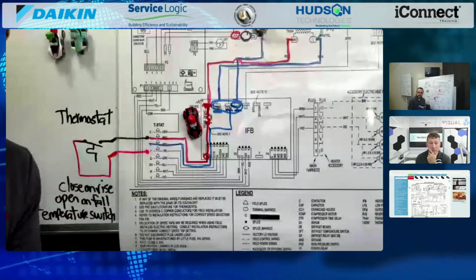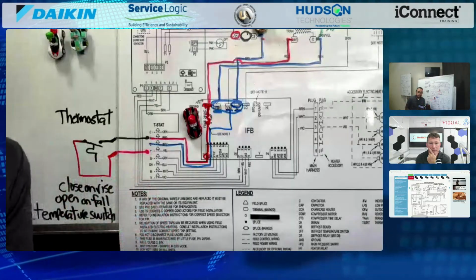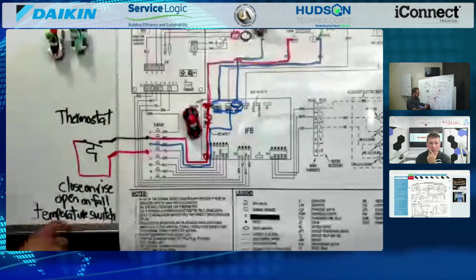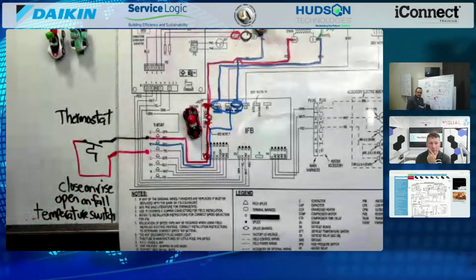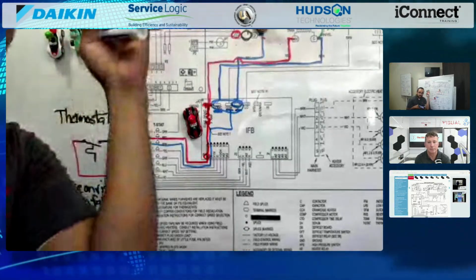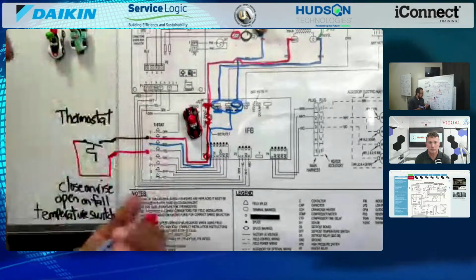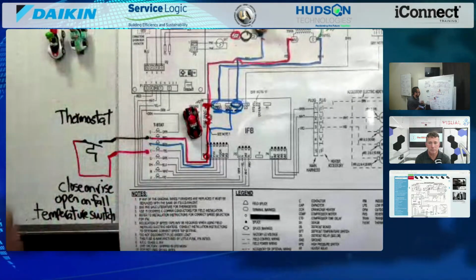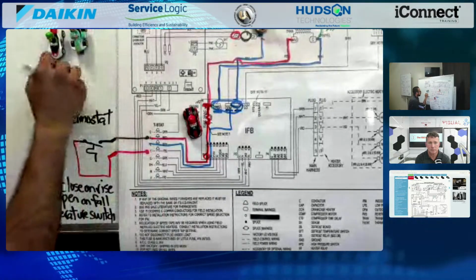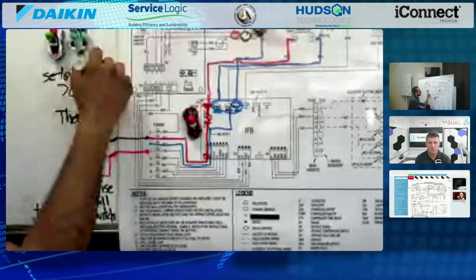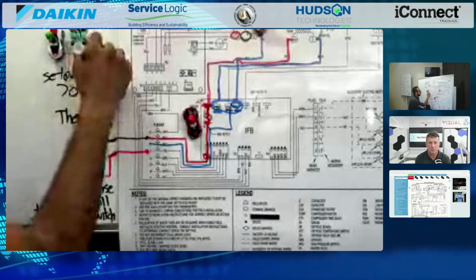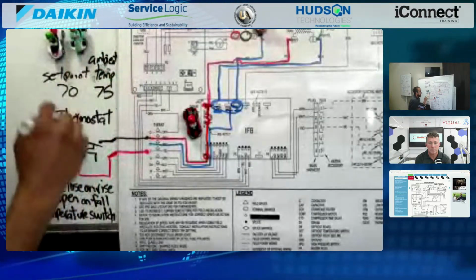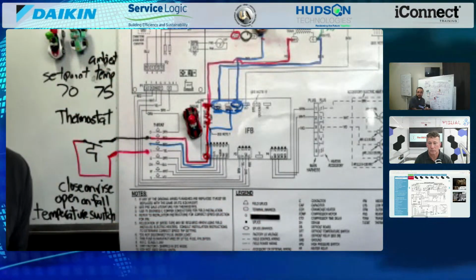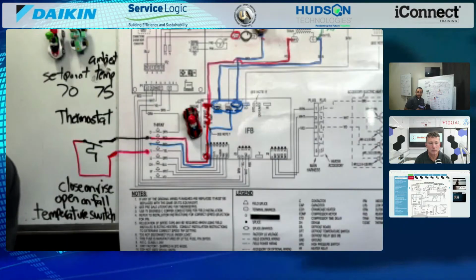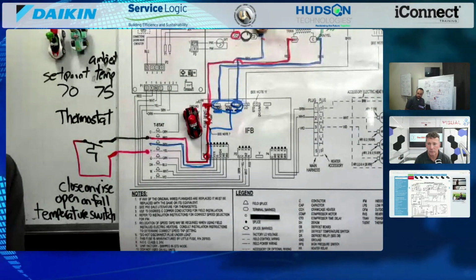Backlight, right? Yeah. But the thermostat is also a switch, right? So you have something that is a temperature switch, close on rise, open on fall. That means if temperature rises, and let's say your set point is 70 degrees, and your ambient temperature is 75, hey, I'm 5 degrees over. I'm going to have a call for cooling. That switch is going to close.